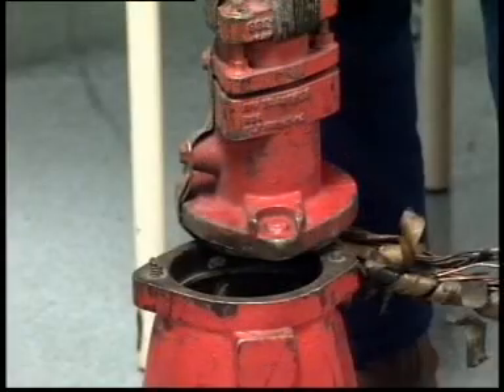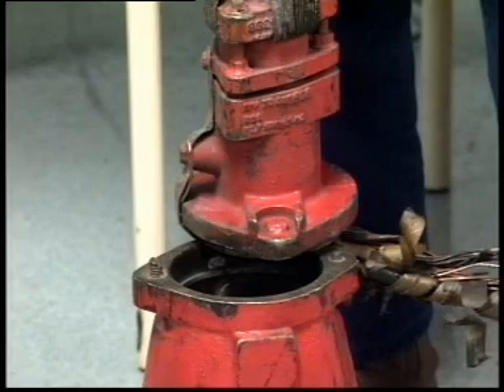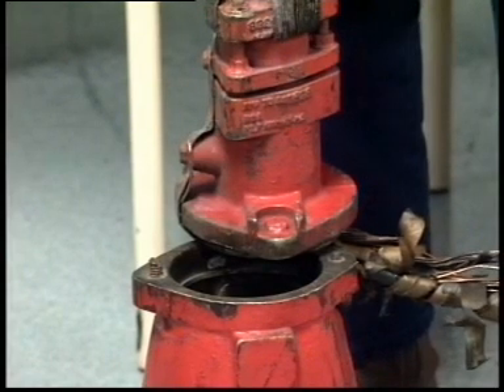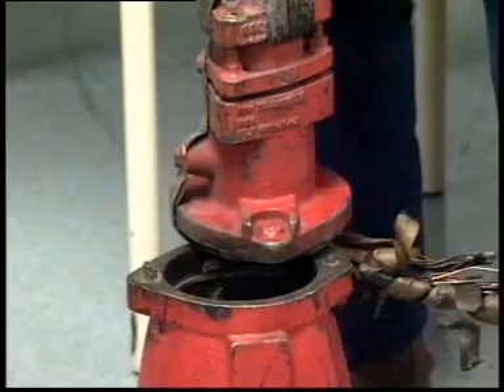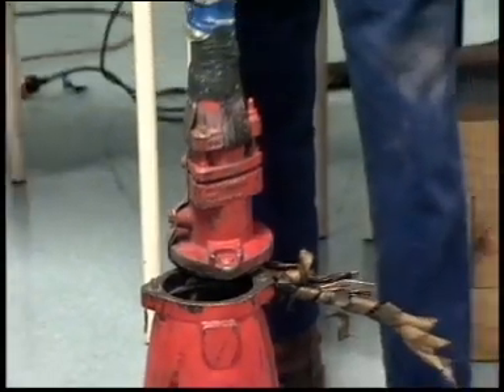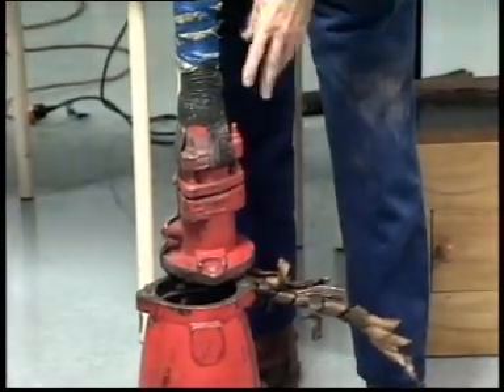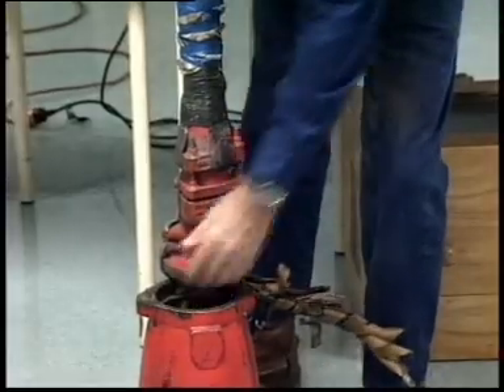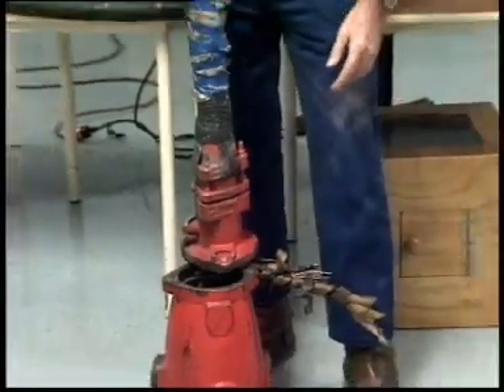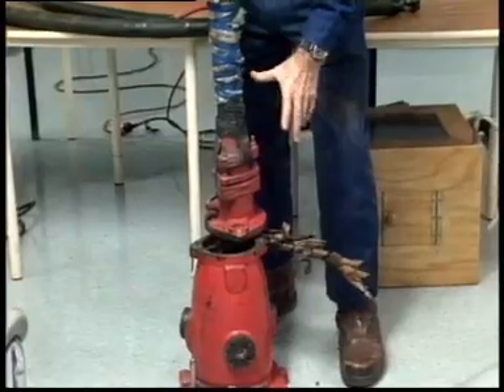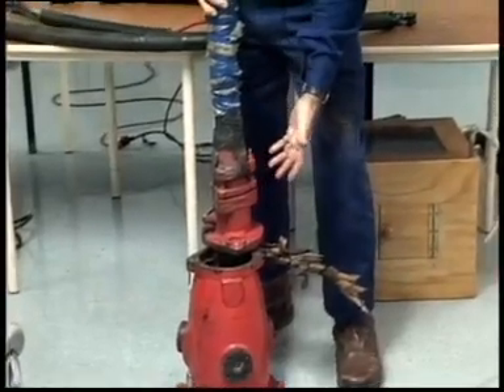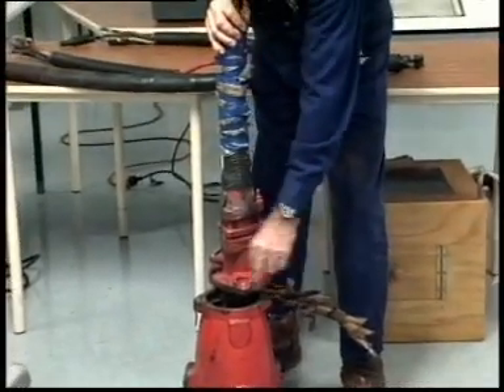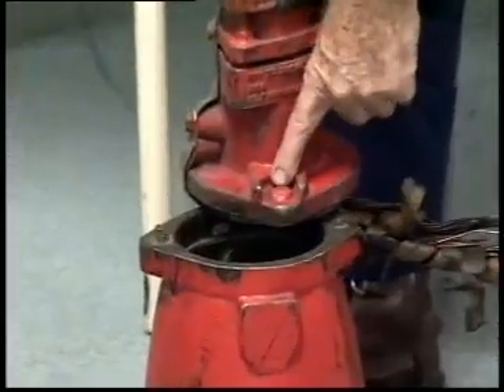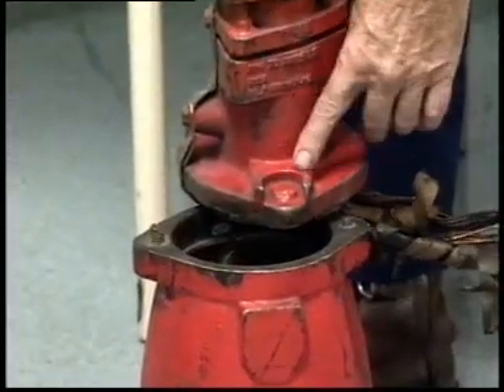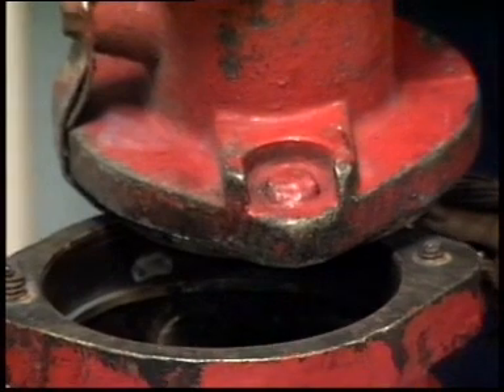This particular plug here was on the surface just up from the portal at an underground mine, and it had been in service for some time, and one afternoon shift about 5:30 in the afternoon, there was a fault occurred in the back end of the plug down inside here. When it occurred, the pressure was so great inside that it blew the complete back end out of the plug. It snapped these 2 half-inch bolts off that are here and left the heads in the back of this section, and it blew this section about 4 metres away.